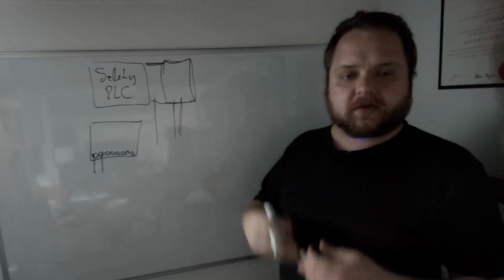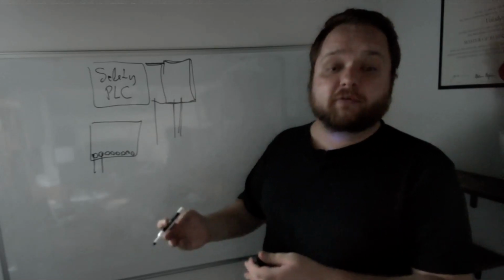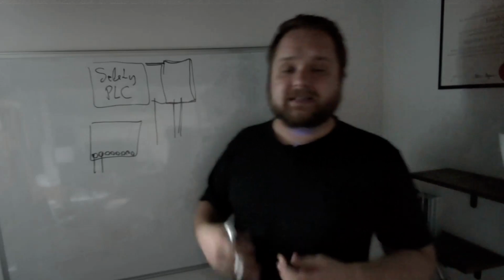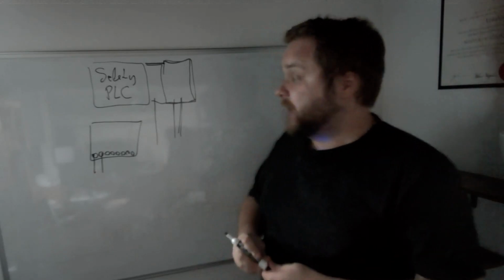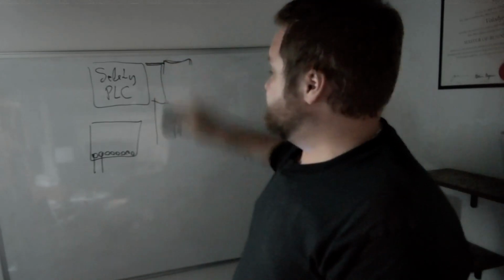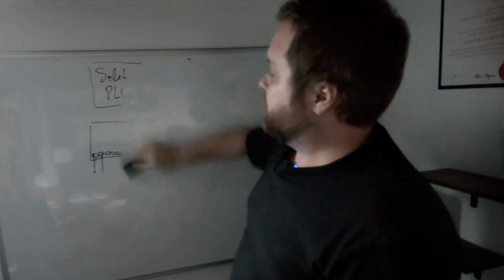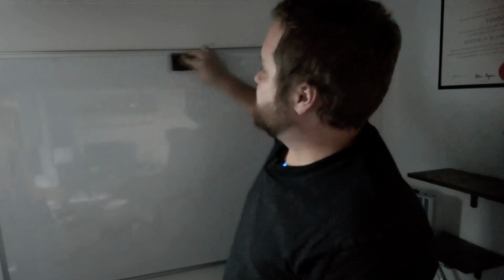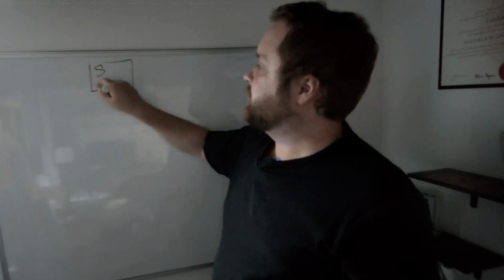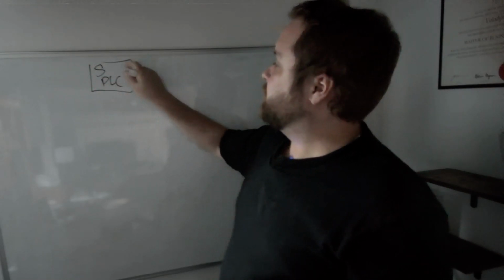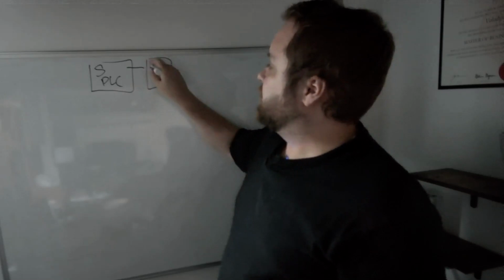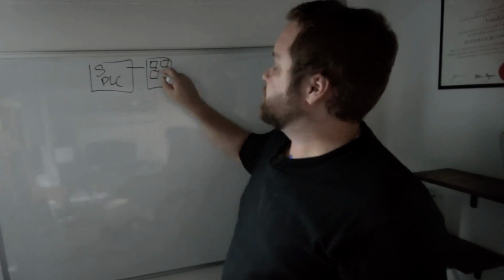There's also now a lot of conversations and a lot of applications of safety over Ethernet IP, or basically TCP IP based protocols. And so it is definitely possible. It is something that Rockwell has released a number of years ago, but now you can also have safety not only via hardwired I/O, but what's called distributed applications. So again, if you have a safety PLC, you can, for example, talk to a switch, and again, there's going to be different configurations that need to be in place.